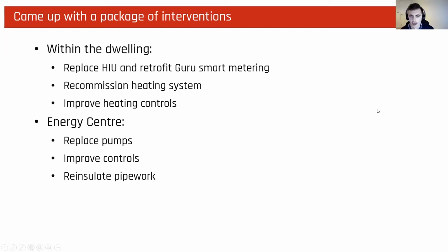So based on the audit findings, we developed a package of interventions, and really this was just focused on addressing those root causes of the identified issues. In the dwelling, that consisted of replacing the HIU to get over those issues identified with reliability on the existing HIU, but also we wanted to take this opportunity to retrofit a metering system that would allow us to remotely monitor the data. That would both help in the short term, so to verify the success of the works, but also long term on the maintenance of the system. We also identified areas where we could recommission the heating system and improve the residents' heating controls.